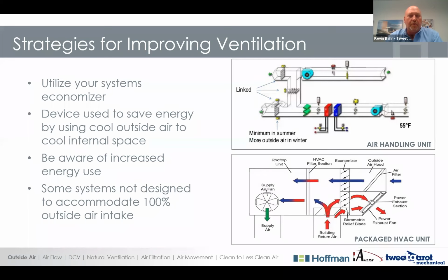You'll notice on the rooftop picture it mentions an economizer, a device often used to save energy and cool the air in your building with cool external or ambient air in certain applications. In this situation, the economizer would be manipulated to increase the amount of fresh air ventilation to your facility. If you notice in the top graphic, it doesn't say the word economizer on the air handler pictorial, but it does show, by the word linked, how the dampers are modulating together. So if you take 100% outside air, your return air goes to 0%.